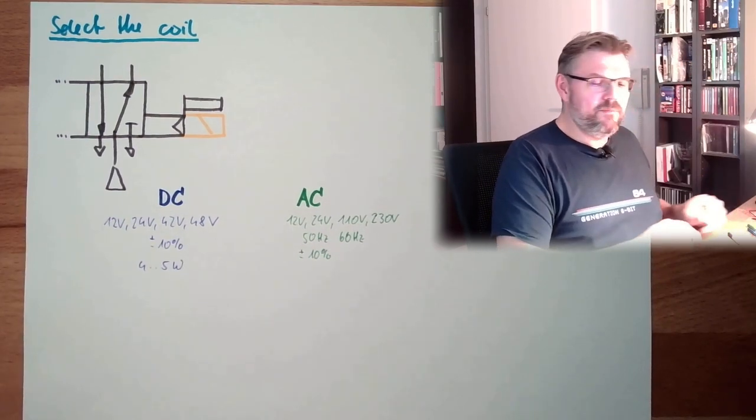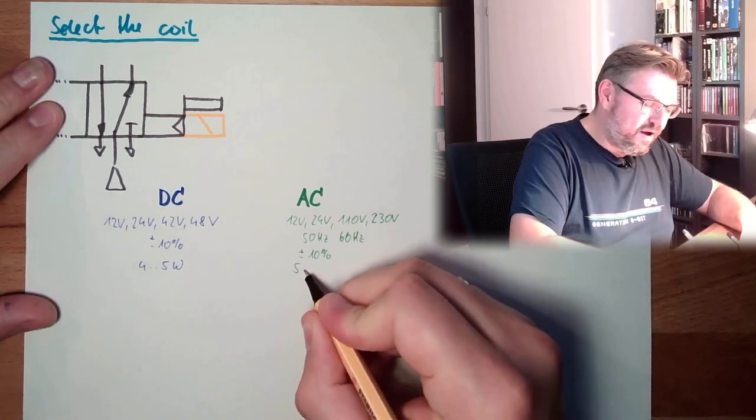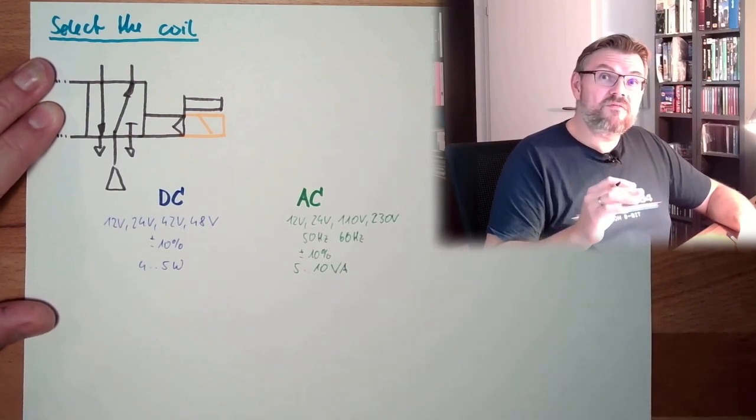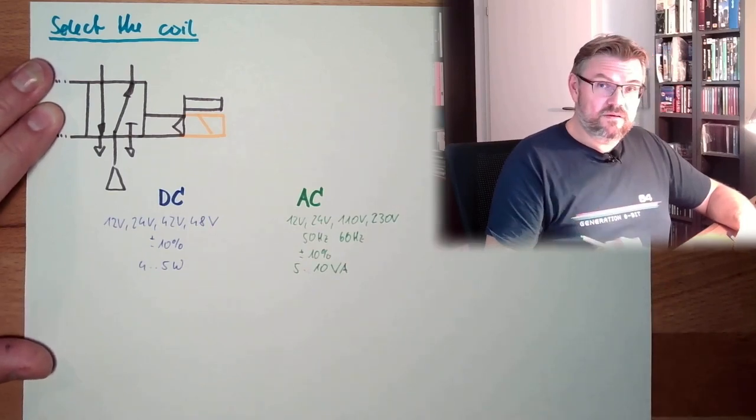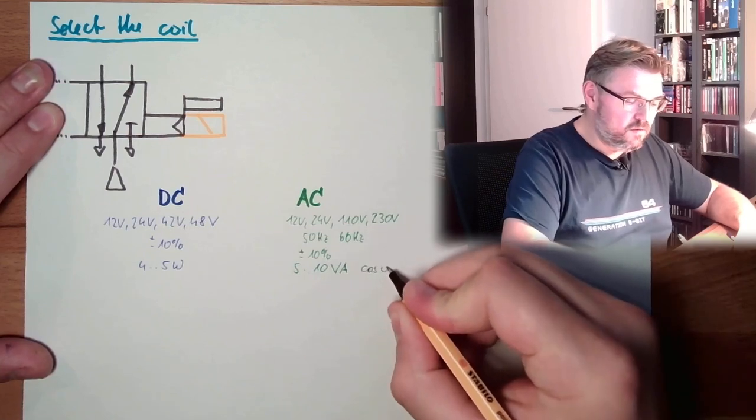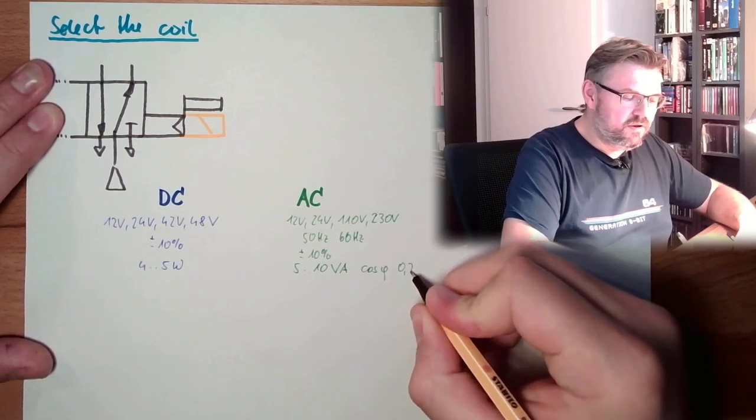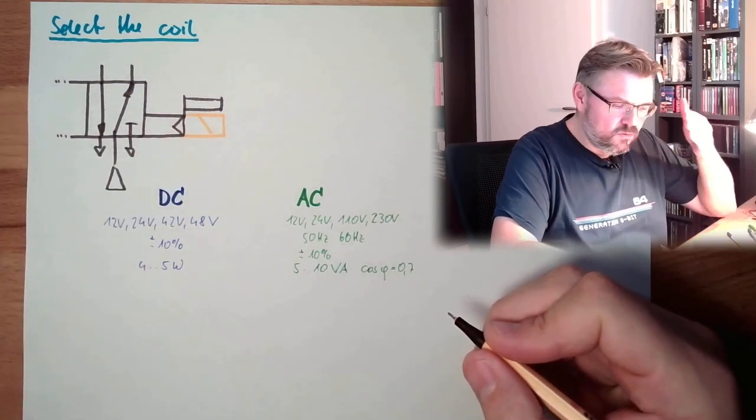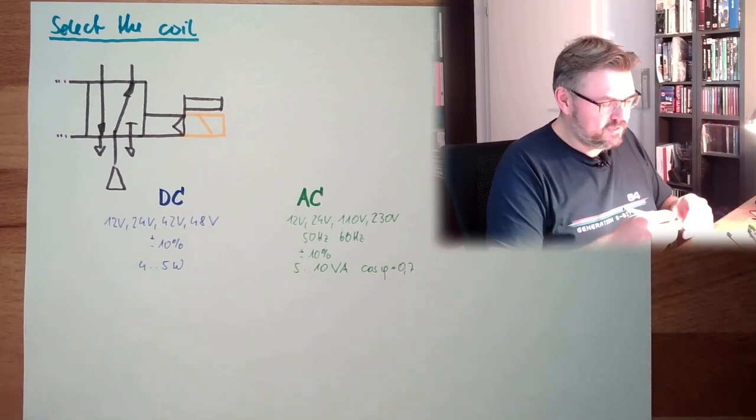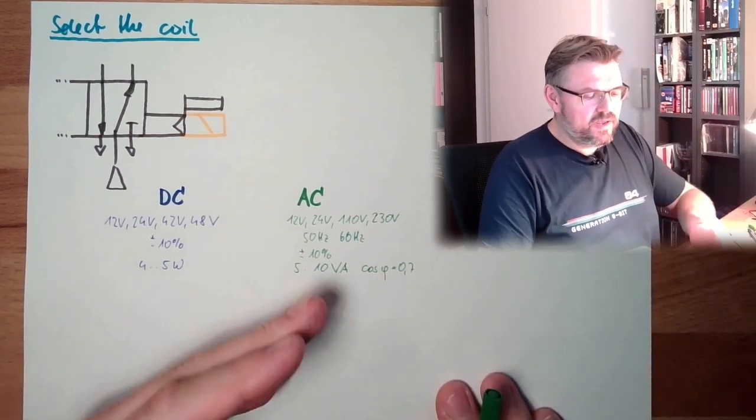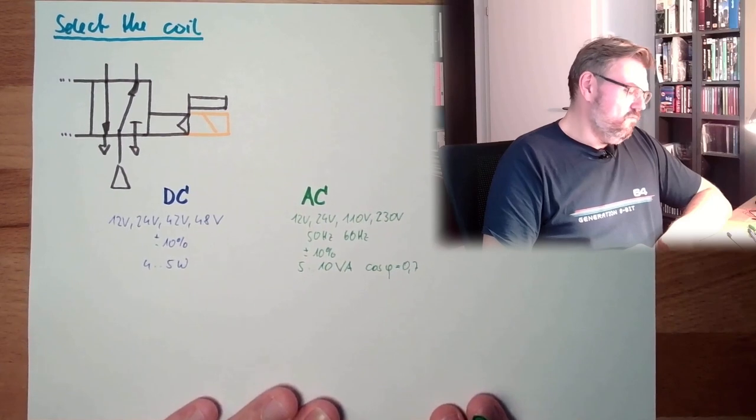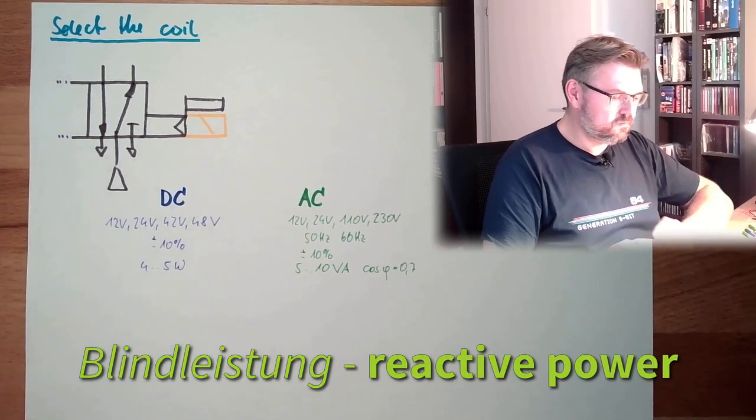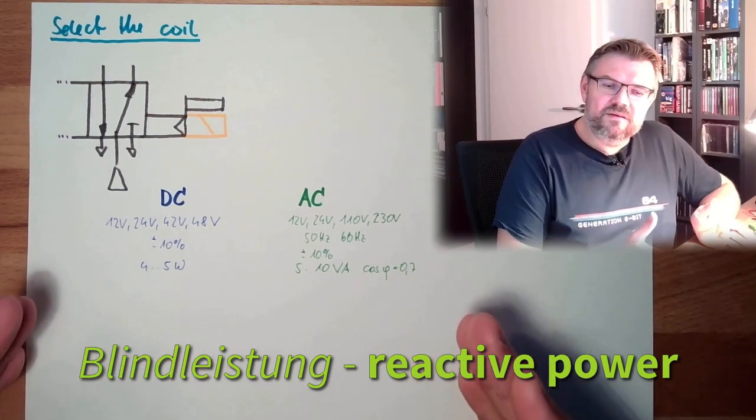Here, we're a little bit above. So we have somewhere between 5 and 10 volt ampere, because there we have also a power factor. The power factor, cos phi, is around 0.7 here. Because it's a coil, it cannot be 1. So only 70 percent of the power consumed by AC are also there for switching. The rest is just reactive power. These are typical values, alright?